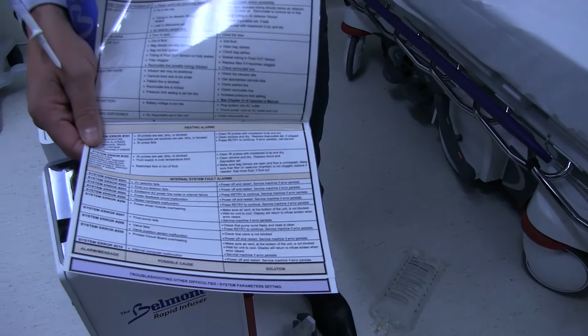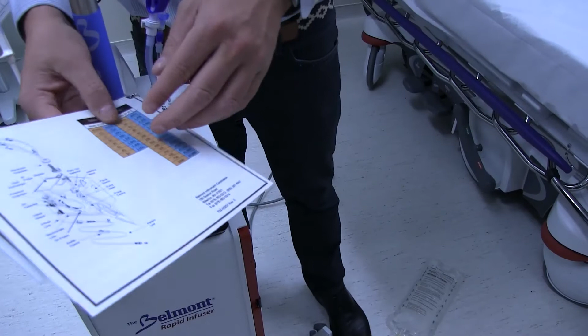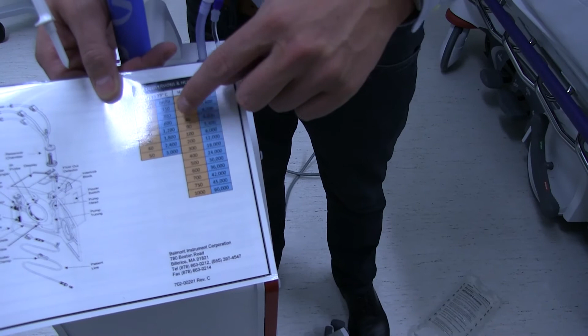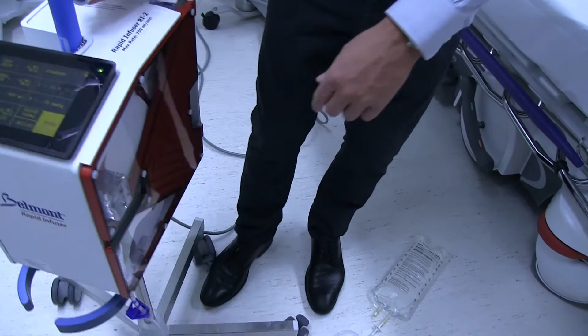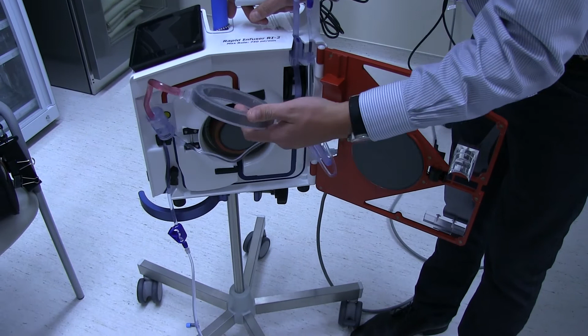And then alarm message, possible cause, solution, with a troubleshooting guide on the back. Name of everything here. And then it's always good to remember that this is always in mLs per minute, so there's a little mL per minute to hour conversion chart there. And then when you're all done, just turn off the machine. The disposable comes out in one piece just like it went in. It's an induction heater, so it never feels warm, but it'll heat up the fluid right away on the way to the patient. And that's the Belmont Rapid Infuser.